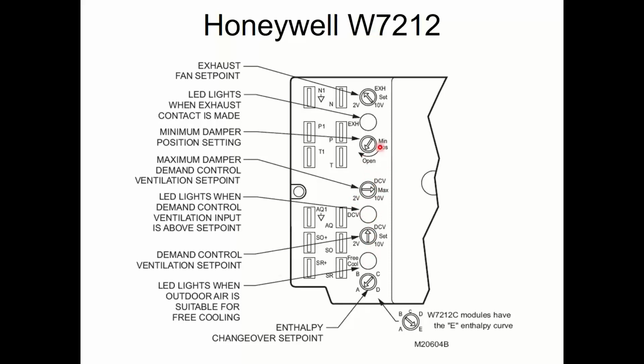Setting up the minimum damper position and the maximum set point for DCV is not intuitive, and almost every HVAC tech does it wrong and accidentally overventilates, which is crazy because the job of the CO2 sensor is to underventilate when people don't show up. Not underventilate, but ventilate less when people don't show up. If you need help with this, once again, let me know. I'll send you a link on how to do this kind of thing.